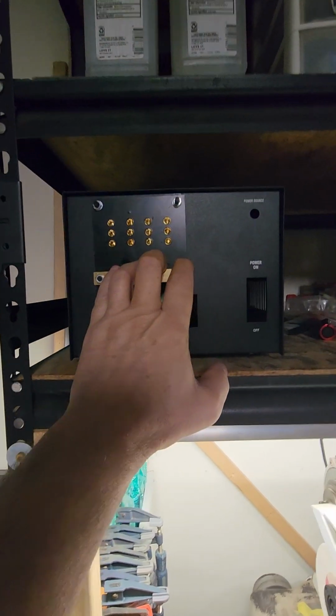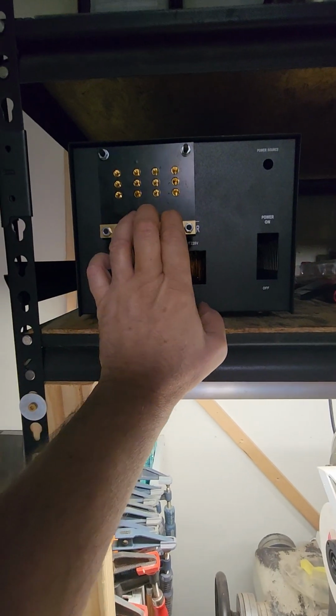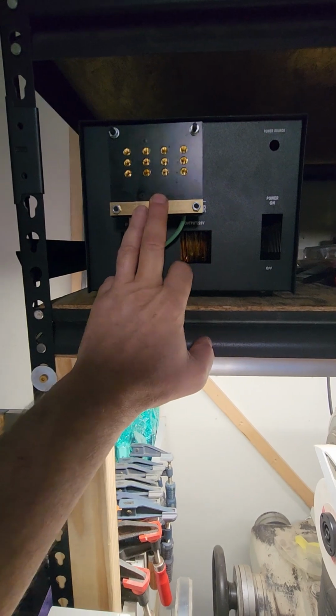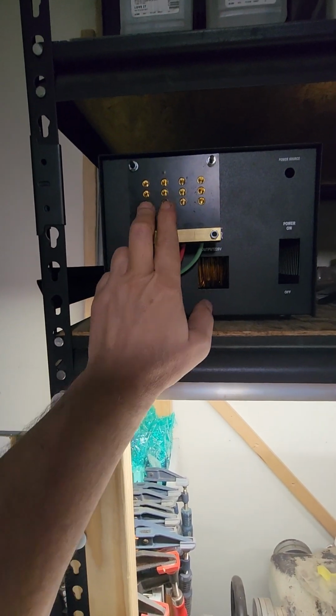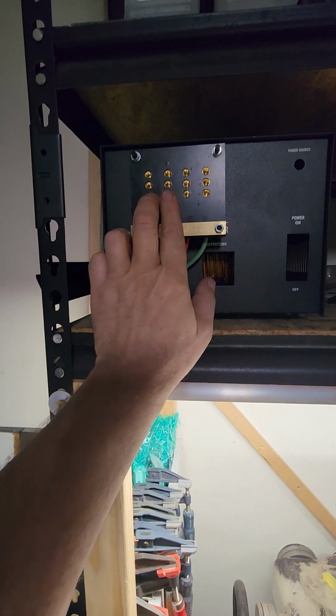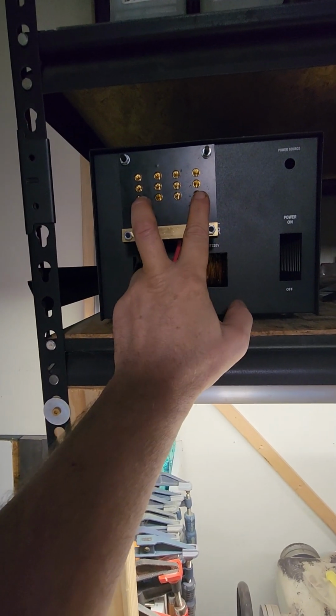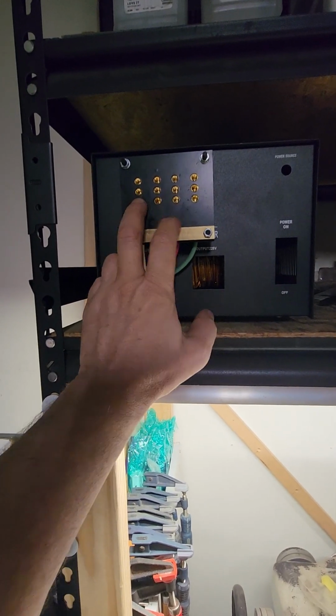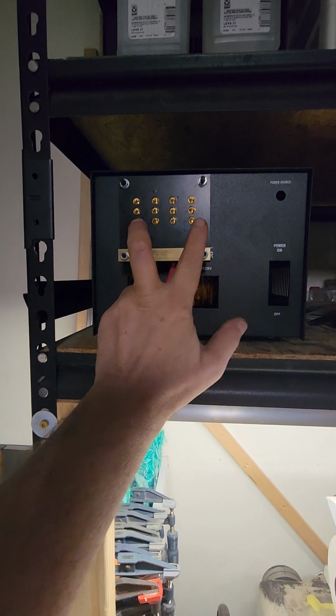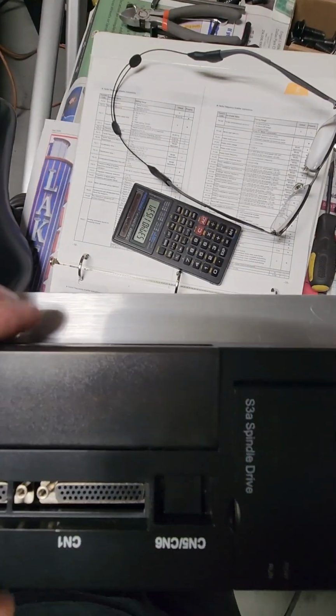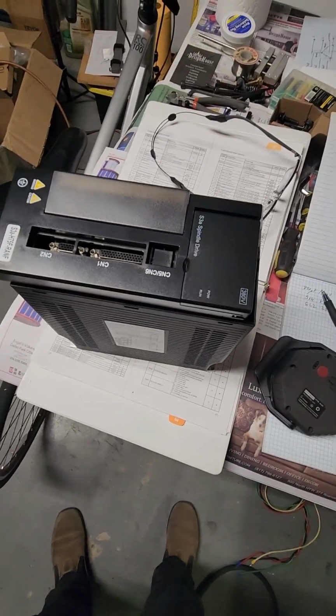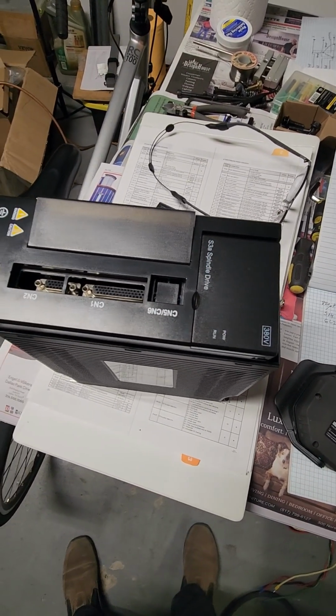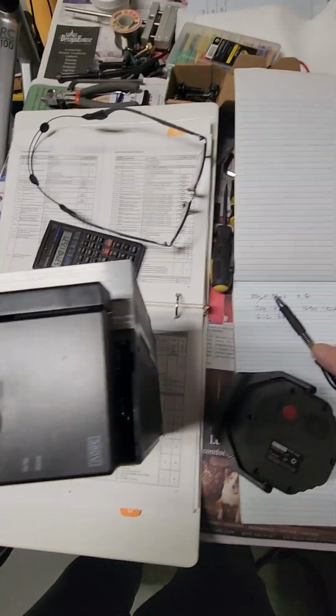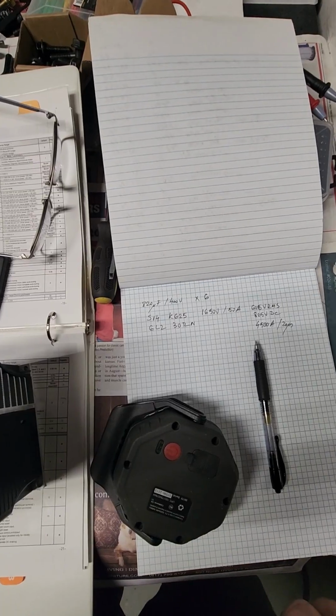So what I think I'm gonna do, I have this, this is an auto transformer, 5 kilowatts. It was from 120 volts to 240, but I modified it and I extended the secondary, well, if you wish, and now I can do multiple combination. If I put 120 here on these two terminals, then from here to here I'm getting 240, and from here to here I'm getting 380. Or if I connect 240 here, then I'm getting from here to here 380. So I think I'm gonna connect my 240 volts here, get 380 out, just one single phase. Connect that single phase here between R and T terminals, and if I hear a clicking noise, that's the relay, the pre-charge relay, to protect the circuit. If I don't hear that, then it's only this inrush current limiters in the way. So we'll see what that gives us.